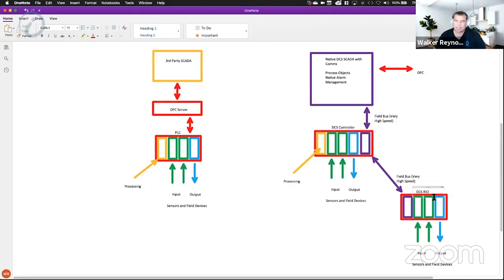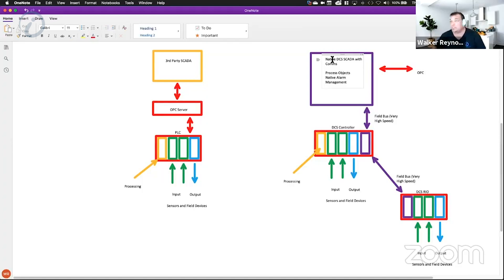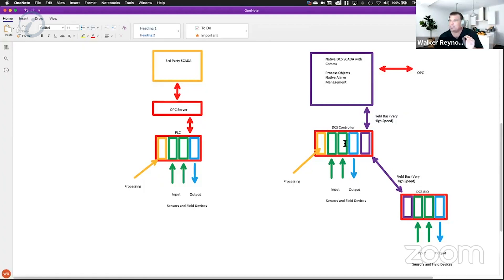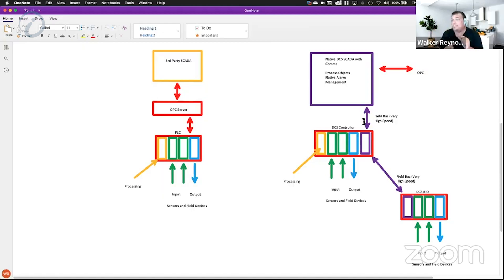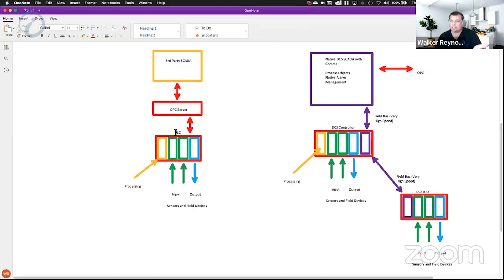There's no OPC server between the DCS controller and the native DCS SCADA. Nearly all DCS systems come with their own SCADA software — whether it's DeltaV or ABB DCS, they have their own software packages designed for the pre-configured objects in the DCS system. The controller talks to the SCADA system over the fieldbus network as well, meaning the SCADA software can control what's happening in the distributed control system much faster. When I make a change to a setpoint, it happens much faster than when using third-party SCADA to OPC server to PLC.